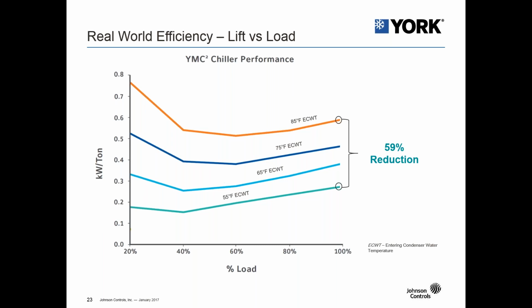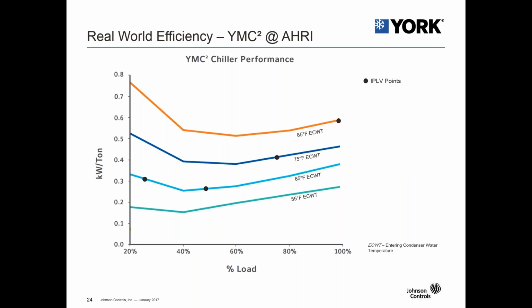So just a 40% reduction in load only gave us a 15% reduction in kW per ton, but just reducing the lift across the chiller by reducing the entering condenser water temperature provides about a 59% reduction in efficiency. So very big opportunity to save energy for customers by utilizing low entering condenser water temperature.